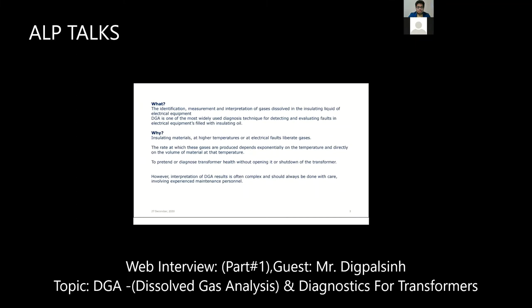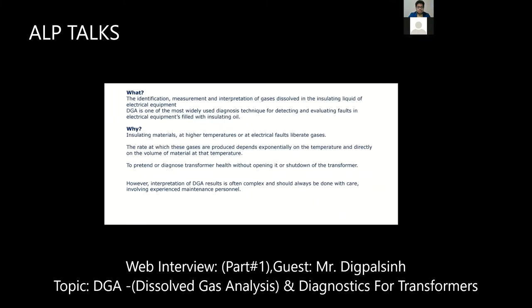So first, what is dissolved gas analysis? Dissolved gas analysis means in every power transformer, so you can say electrical equipment filled with insulating oil, it generates or forms some gases. So we have to identify that gas, then measure the gas, what is the ppm value of the gases, then interpret the gases, what kind of fault is there. So the combination of identification, measurement, and interpretation of gases is dissolved gas analysis.